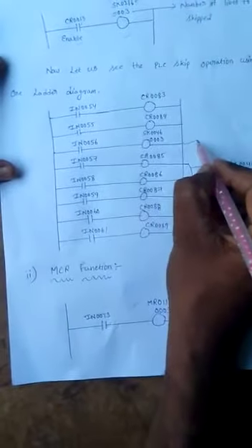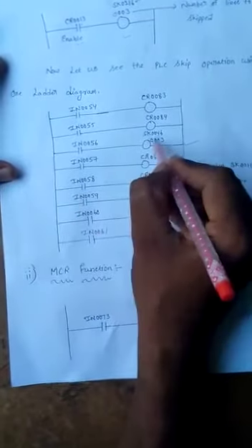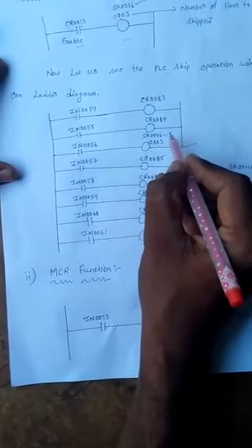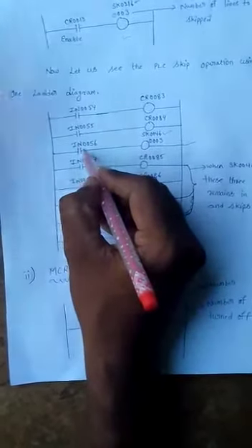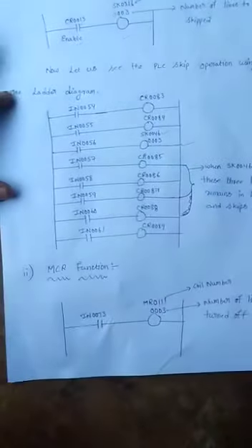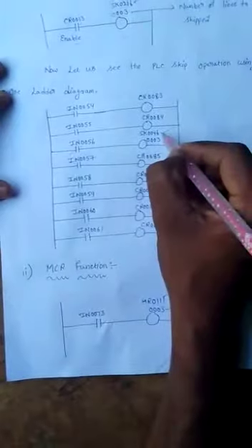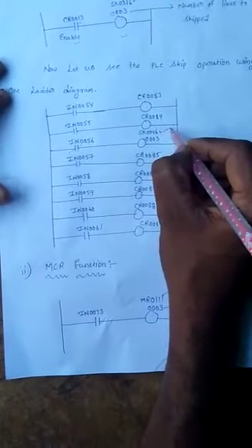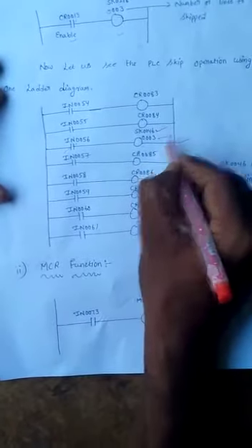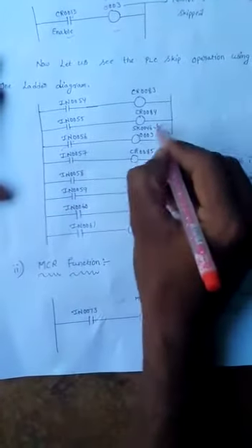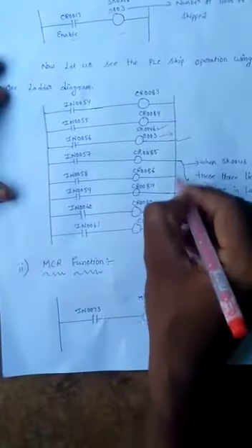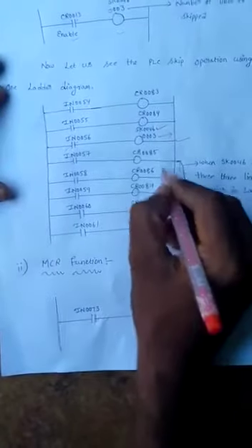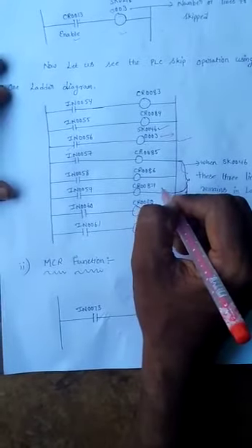Here in the third line, we have our skip function. That means the skip function will perform an operation only when this input contact IN0056 is on. When this input contact is on, the skip function starts its performance. That performance is skipping the 3 lines. This particular syntax performs the skipping of these 3 lines, irrespective of the status of their contacts.